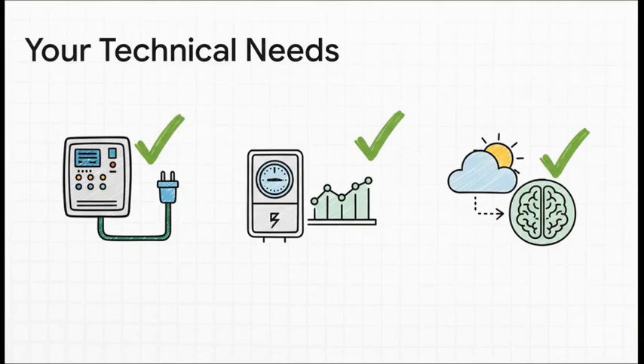First, your building management system, or BMS, needs to be able to talk to the AI. If it's BACnet compatible—basically the universal language for building systems, standard on most platforms from the last 15 years—you're good to go. Second, you need interval energy data to create a baseline so you can track savings, which most commercial buildings already have. And third, you need weather data, which is almost always included with the AI platform itself.